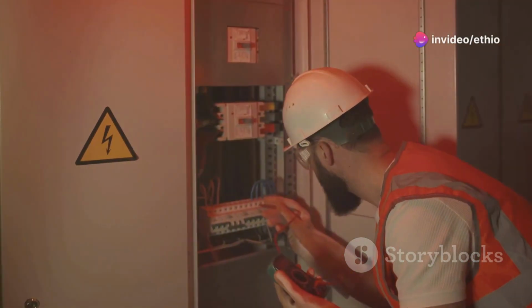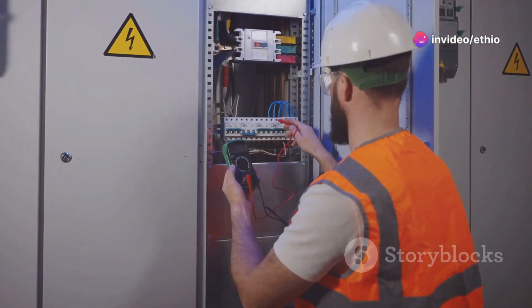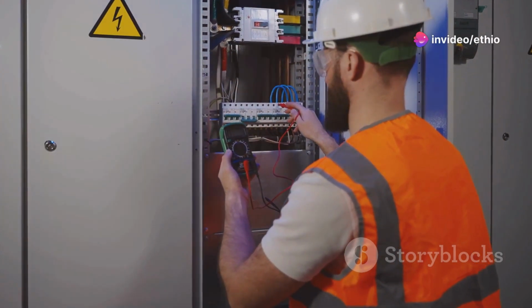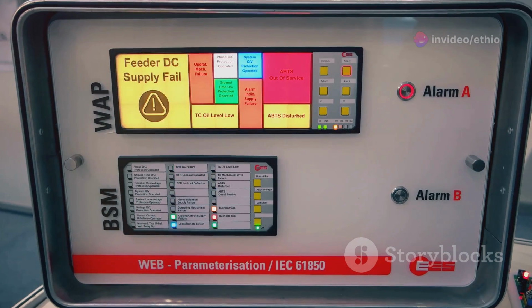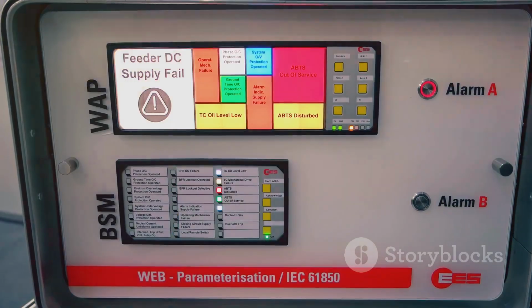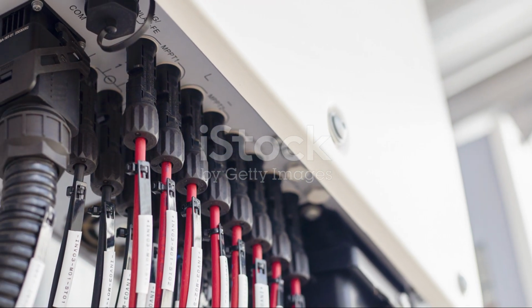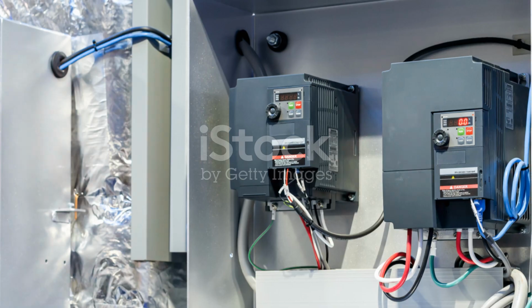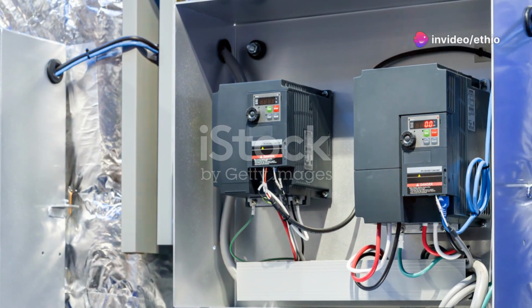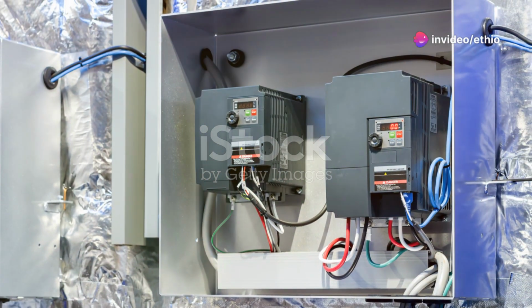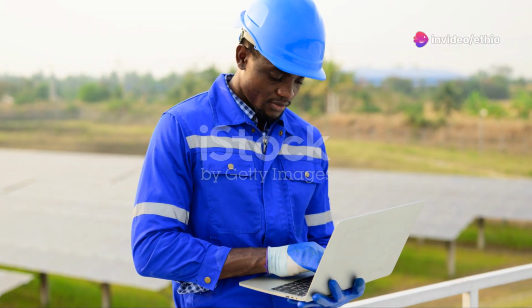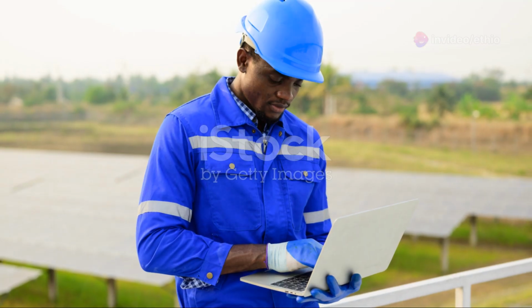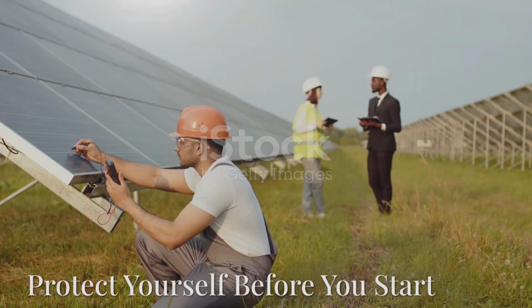Inverters also handle safety features. They control how much electricity flows, protect against overloads, and shut down if something goes wrong. That's why it's so important to keep the inverter in good shape. Understanding what the inverter does helps you spot problems faster. If you notice your appliances aren't running on solar, the inverter is a good place to start.